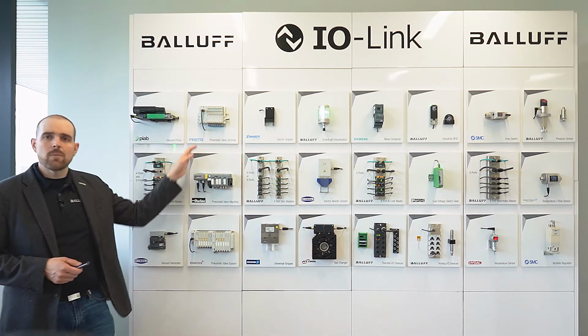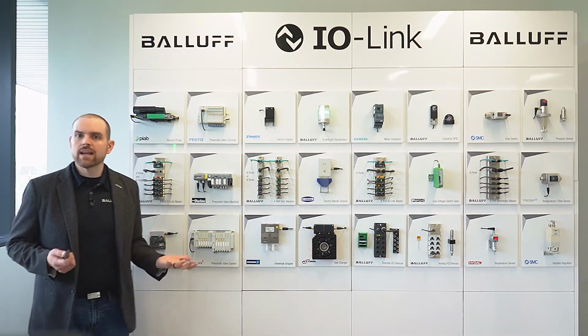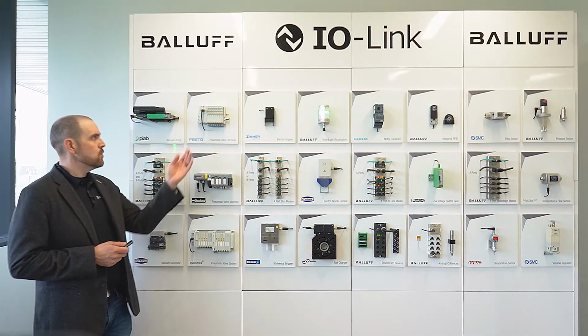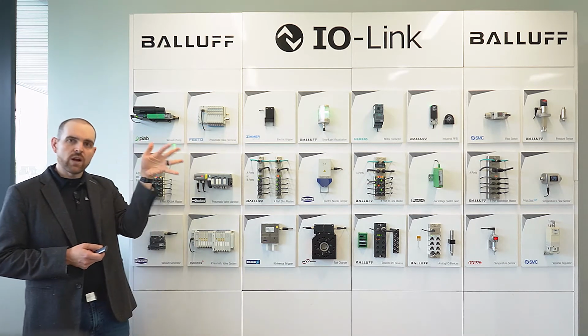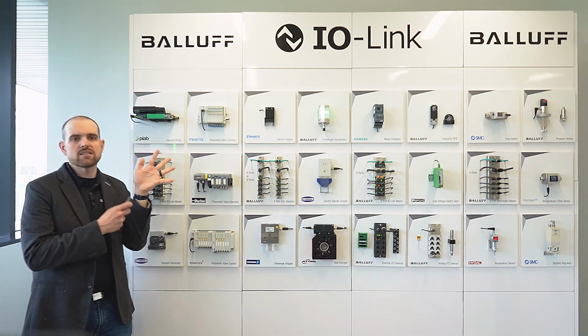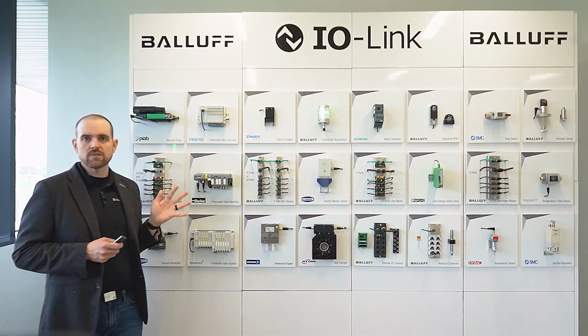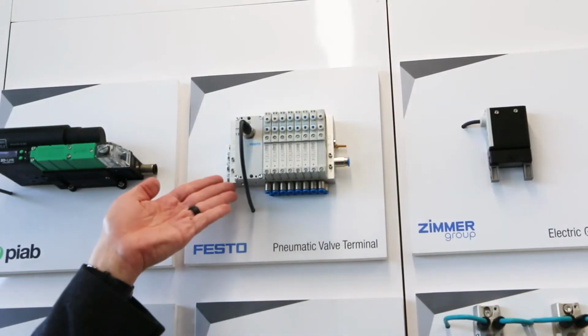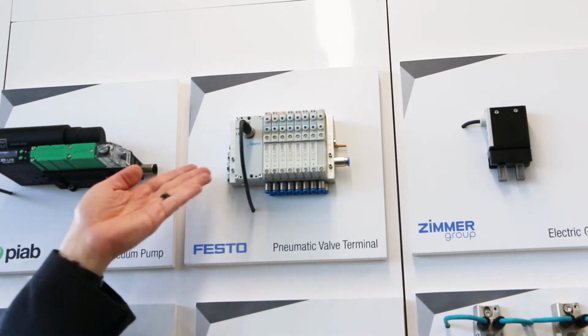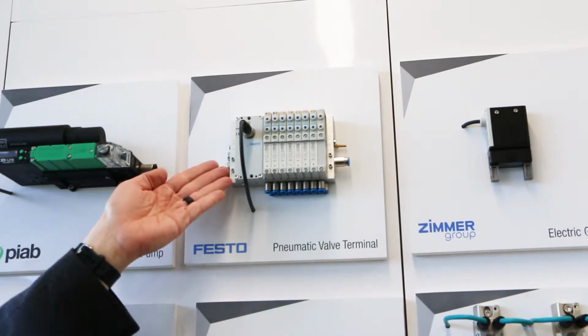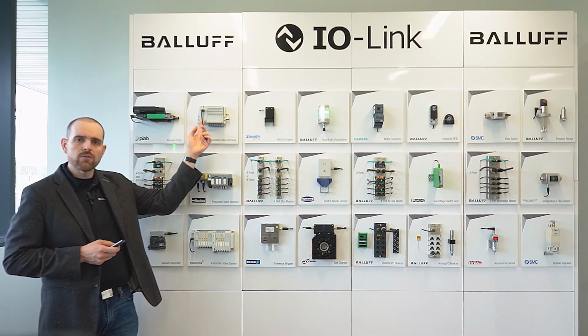Next, you can see here pneumatic valve manifolds. These are very common in automation, right? What's cool about this is instead of having a 25-pin D-sub with all the wires and output cards and short circuit protection you got to put in there, this is one sensor cable. It's a 5-wire cable because it's got to be that B-port style to control the output power for the valves.